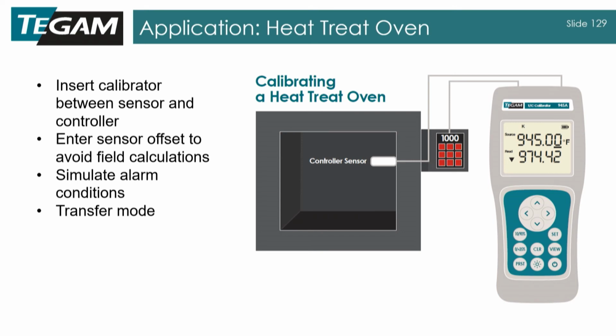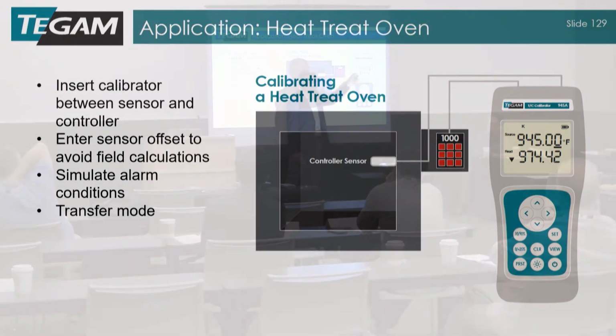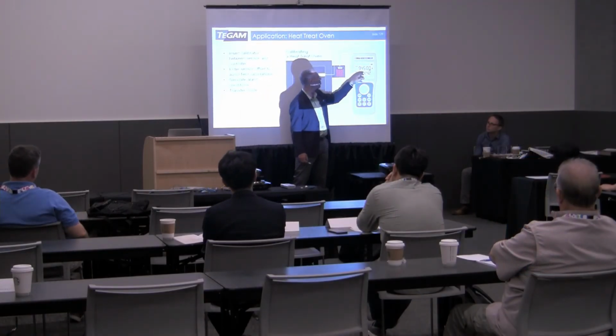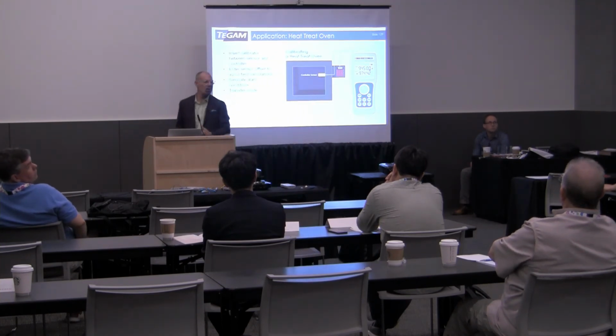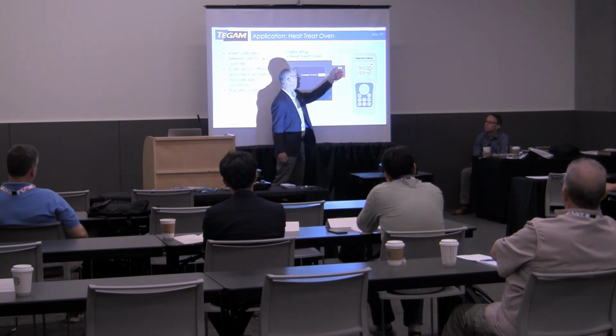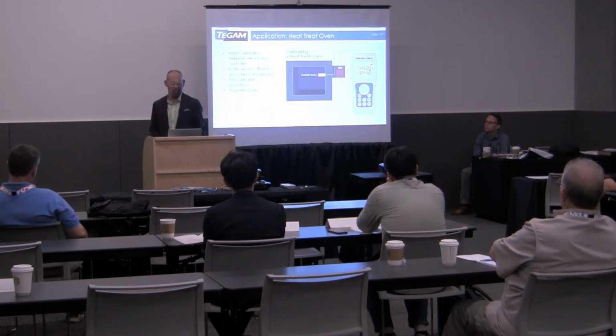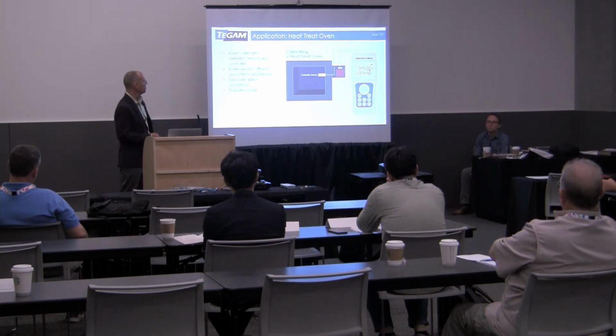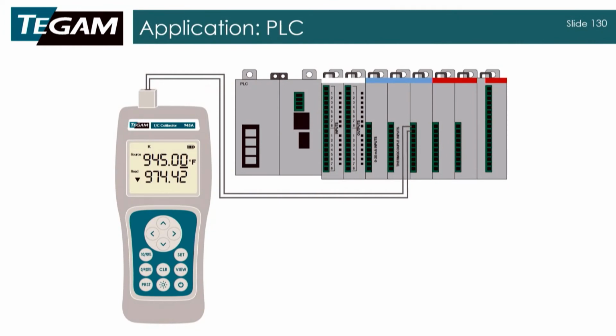So what this calibrator lets you do is you can key in, as Richard did when he zeroed the probe, that offset right into this and set this up in what's called transfer mode. It'll pass the signal that it gets here back out the simulation port, but it'll correct it for the offset. So now you have a corrected thermocouple signal going to the controller, and you can then record your calibration without having to manually calculate that offset. That's handy. This is really a lot like calibrating a transducer, but instead you're calibrating a PLC, just into a set of thermocouple inputs.